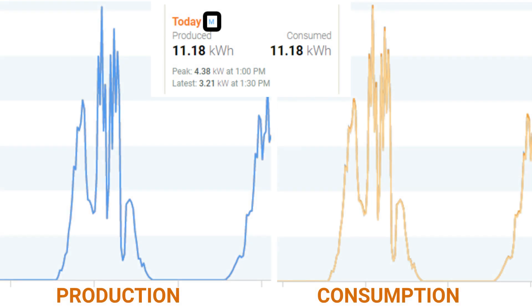In this photo you can see that in the installer portal the values reflected for production are matching exactly what we are seeing for the values of consumption. This is clear evidence of mirroring.